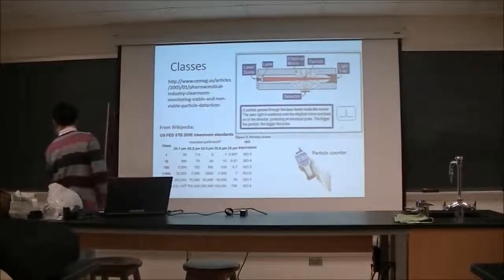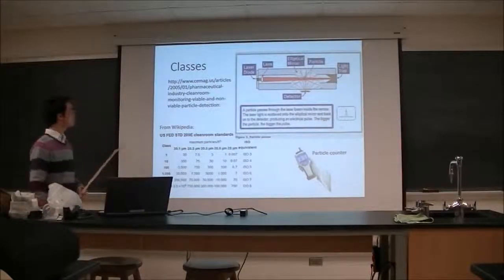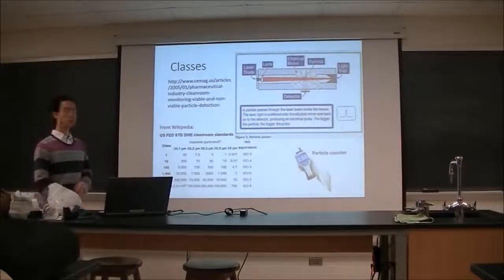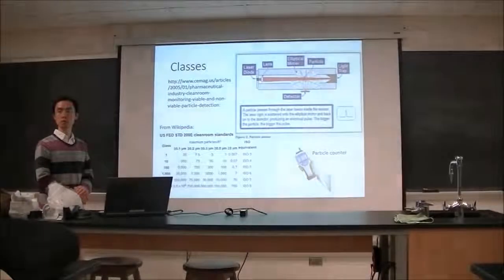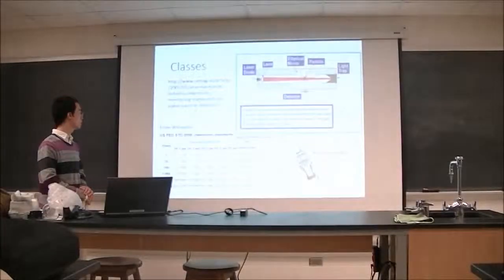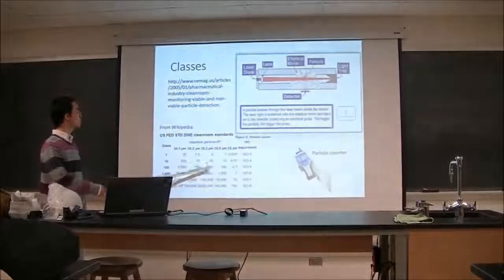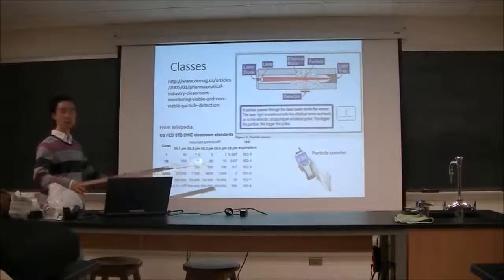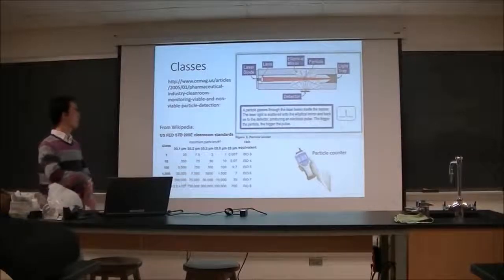And then I have to talk about the classes. So normally, when you talk about clean room, you will hear something like class 1 clean room and class 10 clean room, class 1000 clean room. What does it mean? Basically, it means the number of particles in a certain volume.